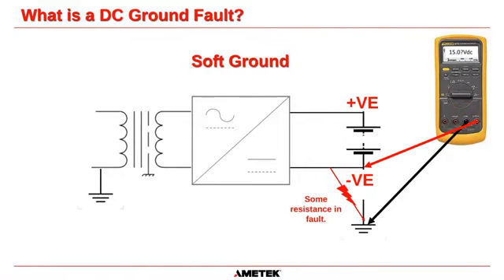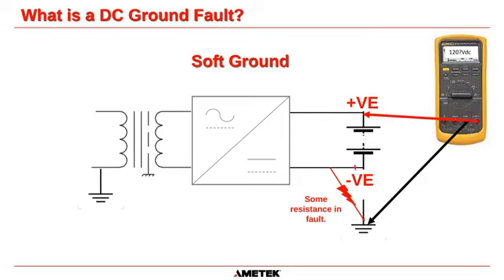If you had a soft ground, where there is some resistance, usually in the kiloohms, then things get kind of fuzzy. In this circumstance, the connection is now between the negative and ground, and there is some resistance in there. So when we measure from negative to ground, we are actually getting a voltage of 13, 15 volts. There is some voltage between the two because it's not a hard short. And then if you went between positive and ground, when you have a soft negative ground fault, you're going to get about 120 volts, the other proportion of that full voltage to ground. Okay, that's a soft ground fault. Soft ground faults are harder to locate than hard ground faults, but there is a tool that can help you with that, which we'll get to later.